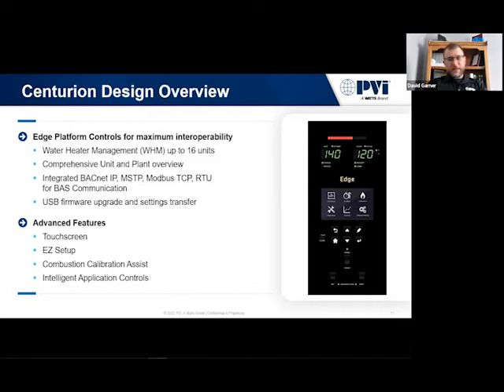In addition, it has a security protocol built into it that all you have to do is enable, and it will only accept commands from that server, that MAC and IP address. So if someone has concerns about someone hacking into the BMS system and changing set points or disabling the equipment, if it doesn't recognize that server, it won't accept any command prompts from it.